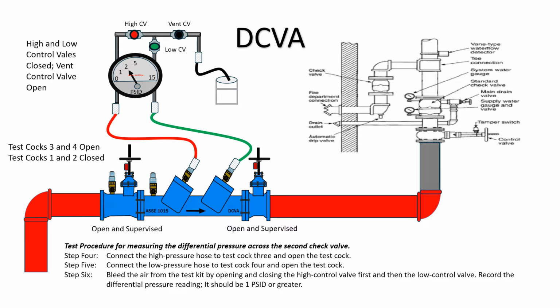Test procedure for measuring the differential pressure across the second check valve, DCVA. Step 4. Connect the high-pressure hose to test cock 3 and open the test cock. Step 5. Connect the low-pressure hose to test cock 4 and open the test cock. Step 6. Bleed the air from the test kit by opening and closing the high control valve first, and then the low control valve. Record the differential pressure reading. It should be 1 psid or greater.